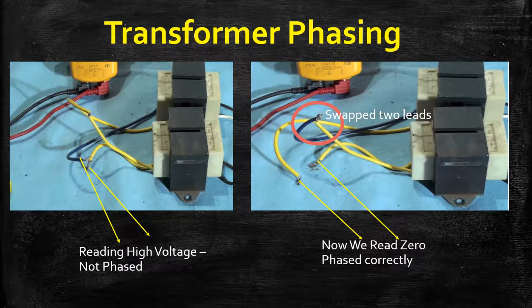To determine if two transformers are phased correctly, take a voltmeter and read two leads on the output voltage. If you read high voltage, the transformers are not phased correctly. Swap the connected power leads, and then you should read 0 voltage and the transformers will be phased correctly.